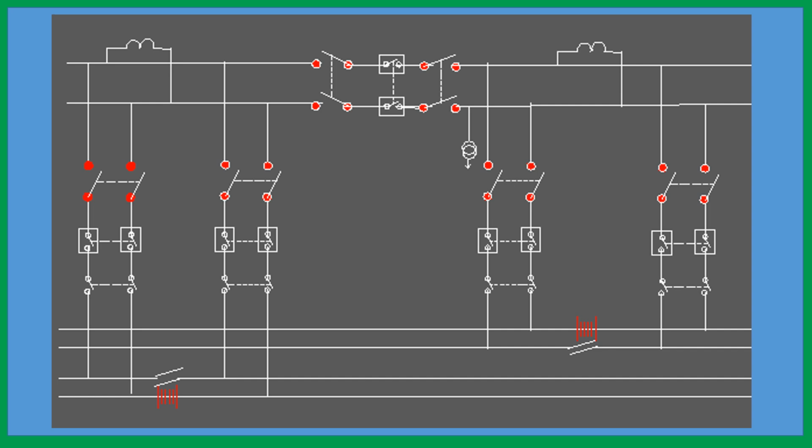Simply you connect the plus 25 to the incoming side of the circuit breaker or interrupter, and outgoing you give it to the OHE. Output will be given to the OHE, and the mid portion of the auto transformer will go to the railway neutral track, traction railway track. So in this way you can convert it.